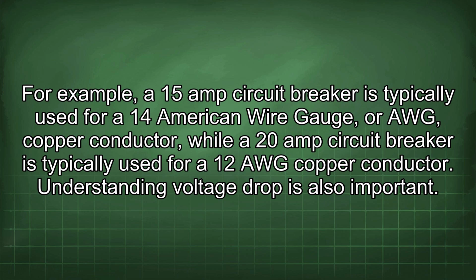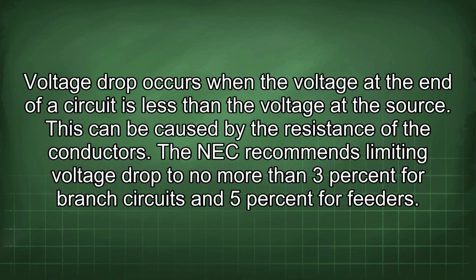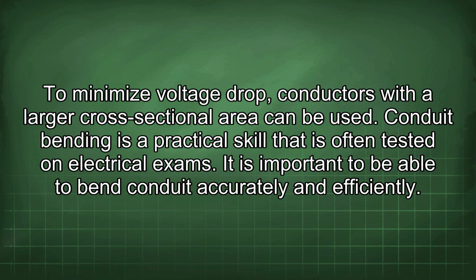Understanding voltage drop is also important. Voltage drop occurs when the voltage at the end of a circuit is less than the voltage at the source. This can be caused by the resistance of the conductors. The NEC recommends limiting voltage drop to no more than 3% for branch circuits and 5% for feeders. To minimize voltage drop, conductors with a larger cross-sectional area can be used.